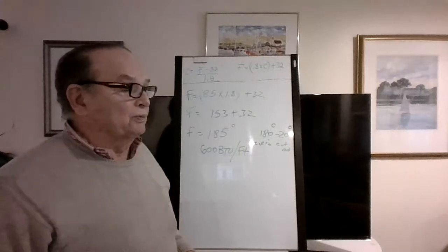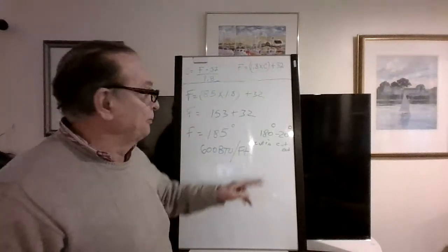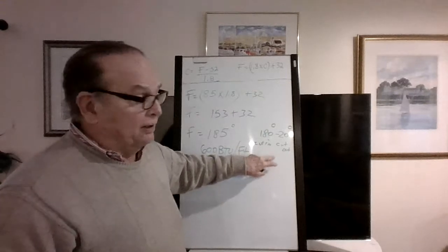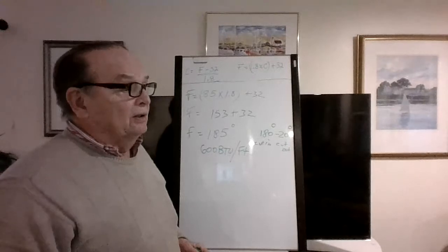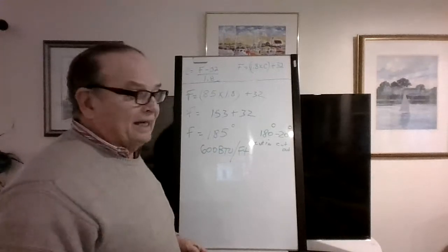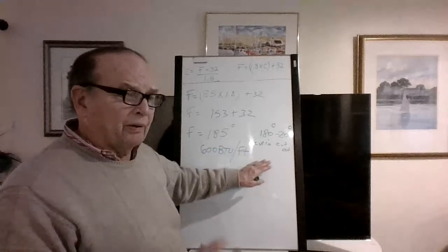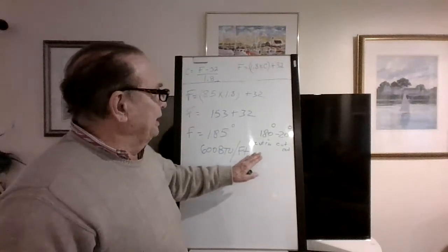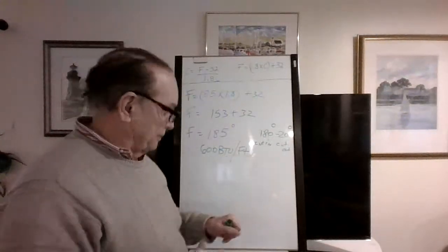Now, the new boilers are much more efficient than the majority of them that I was more familiar with years ago. There were some very efficient boilers, high efficiency, up around 90, 95%, but not that many. And there was always the problem with the condensate when you get over about 87%. In any case, keep that in mind. Cut in, cut out.